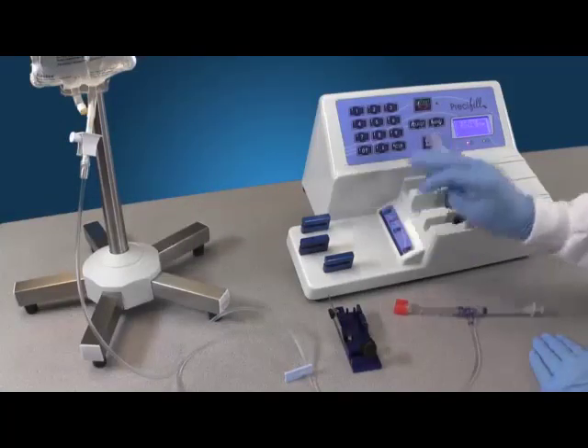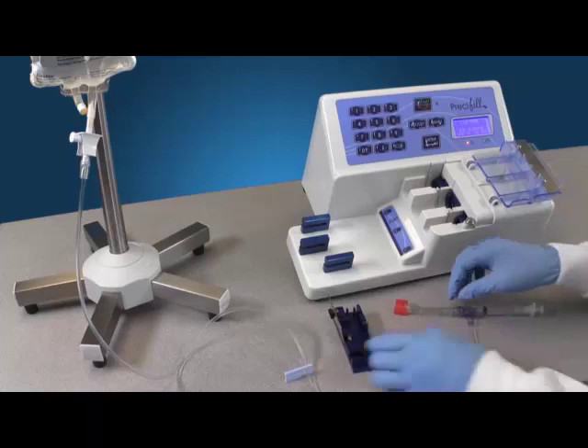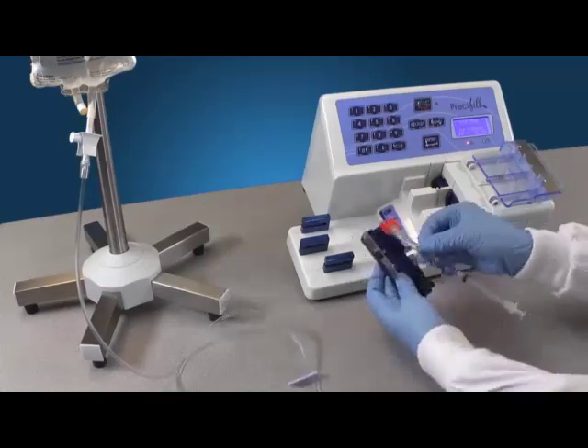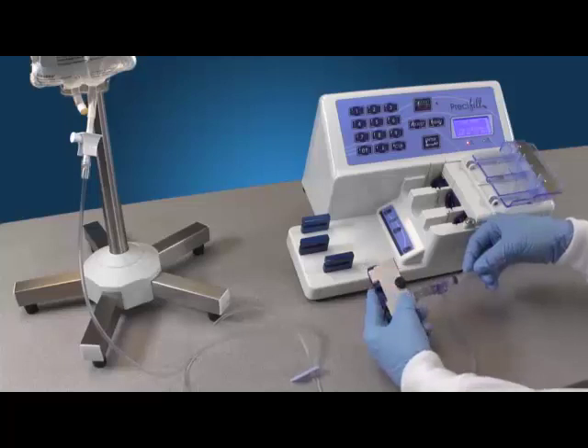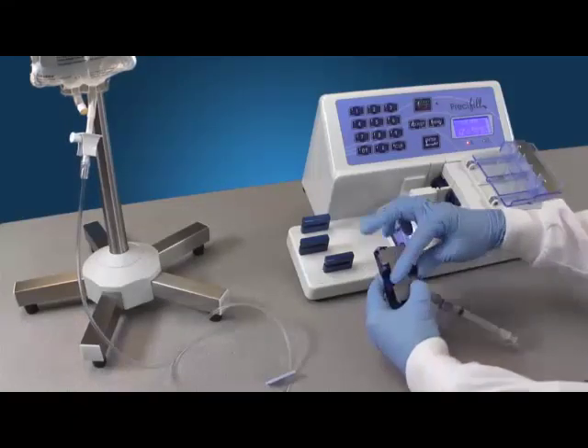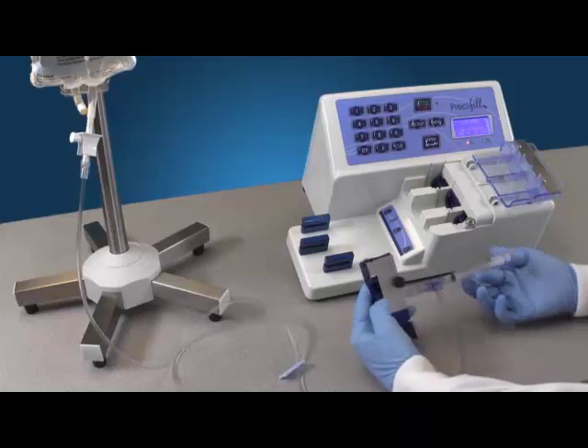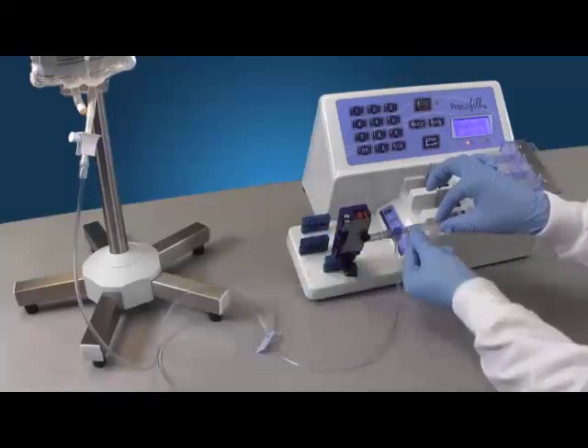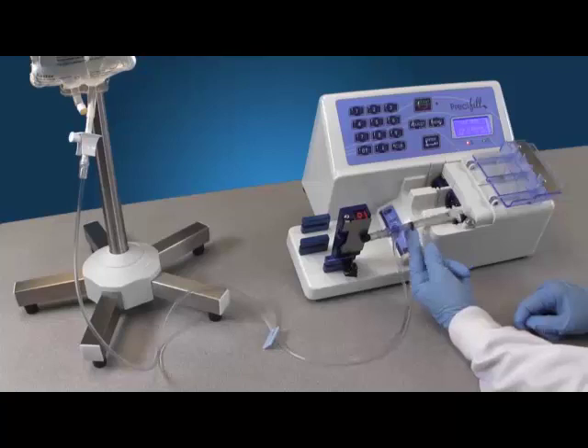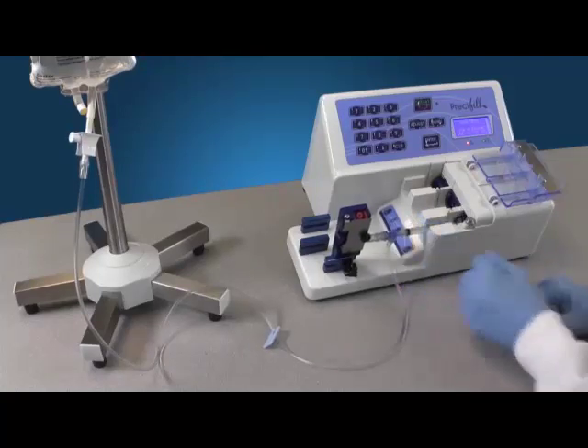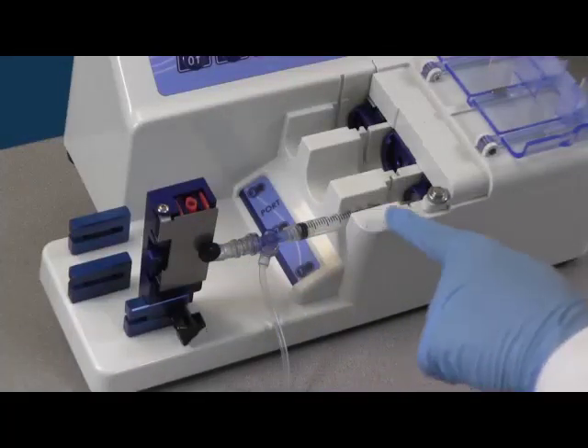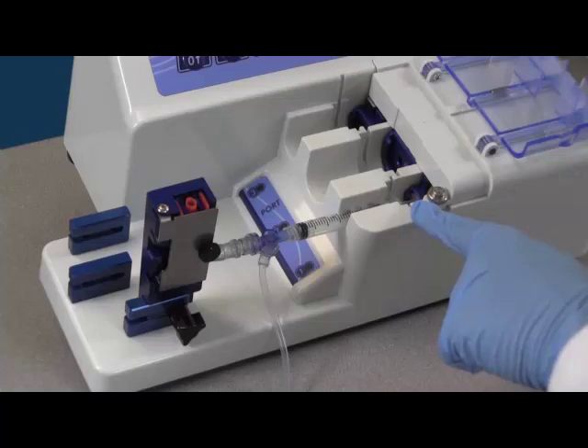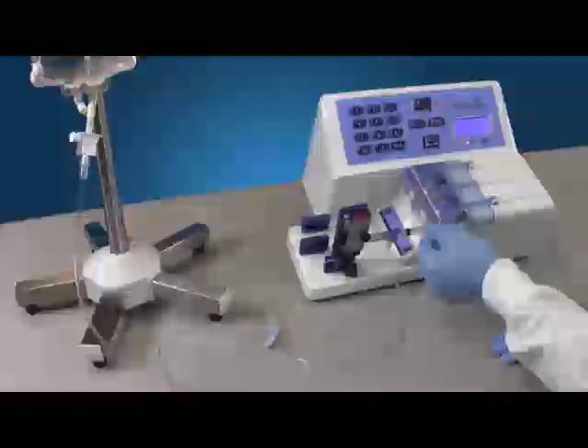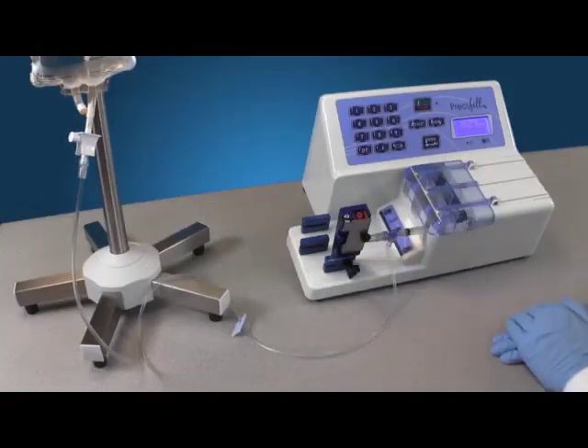To install the tube assembly, raise the blue cover. Place the tubing set into the block holder and tighten the finger screw on the metal door until firm. Be sure not to over-tighten the screw. Slide the block holder onto the appropriate post opposite the active port and install the master syringe into the selected port. The syringe plunger and finger flanges on the barrel must be inserted flat side down and securely into the grooves. Now close the cover and fasten the block holder to the post.